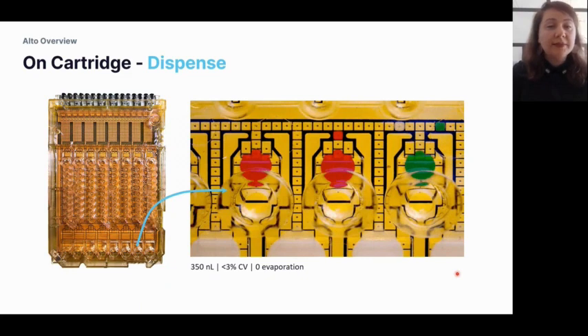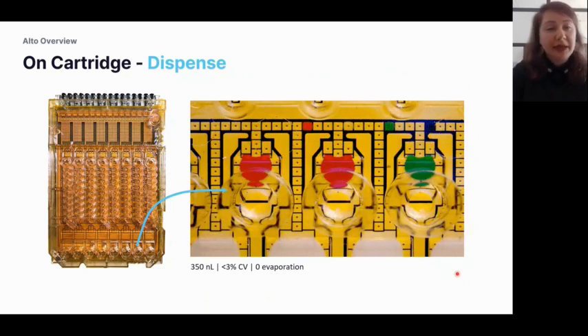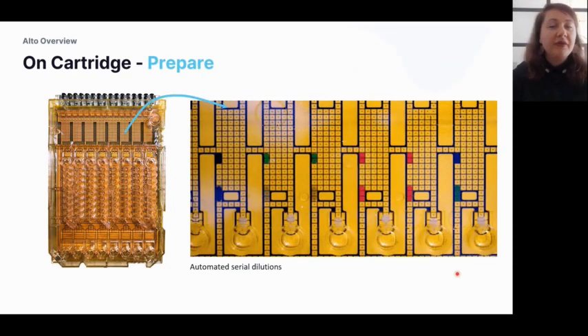From the two-microliter wells for ligand and analytes, only 350-nanoliter-sized droplets are dispensed with high accuracy of less than 3% CV. Because aqueous solutions are found within a silicone-based oil, there is no evaporation. Those nanoliter-sized droplets are taken to the mixing area, where mixing, splitting, and merging occur. Running buffer droplets are mixed with sample droplets to perform automated serial dilutions — five serial threefold dilutions each — and analyte concentrations are queued from lower to higher.